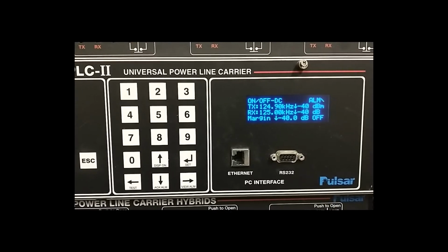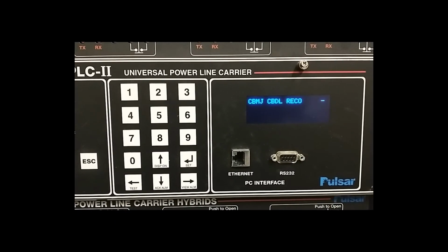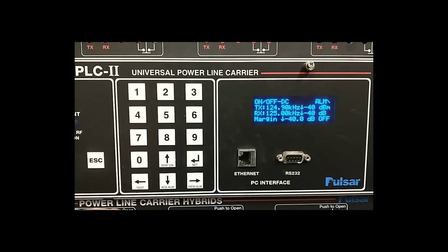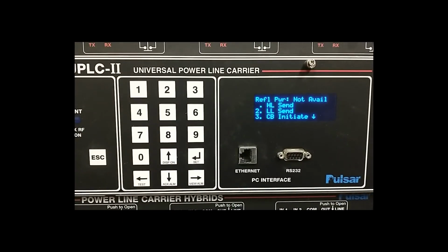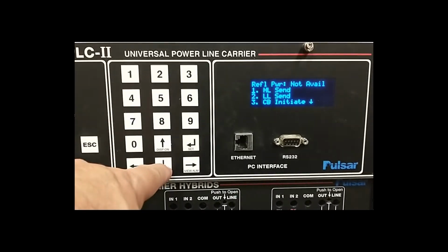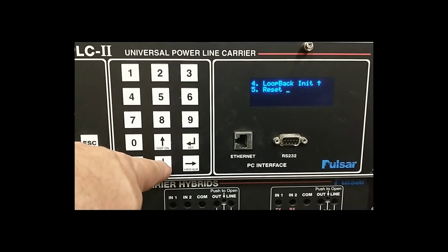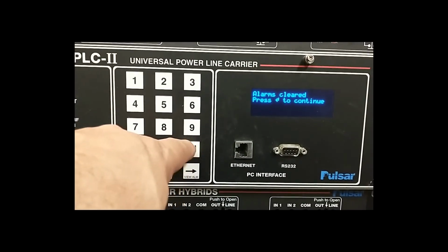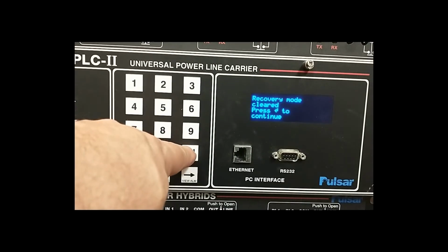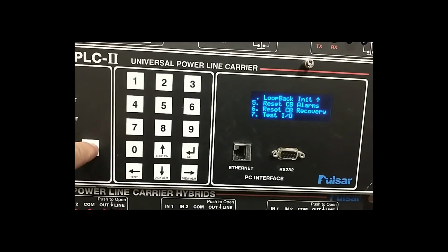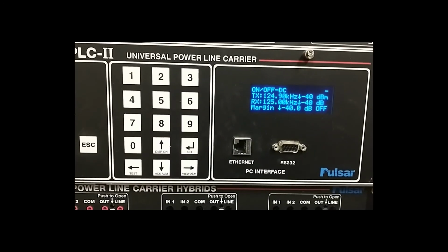If testing or commissioning the checkback system or wanting to clear a nuisance alarm, the recovery and major and minor alarms may be cleared from the front panel under the test menu. By pressing the test button, scrolling down, and activating the Reset Checkback alarms and Reset Checkback Recovery. Once reset, the checkback alarms will be cleared on the display as well as any programmed outputs.